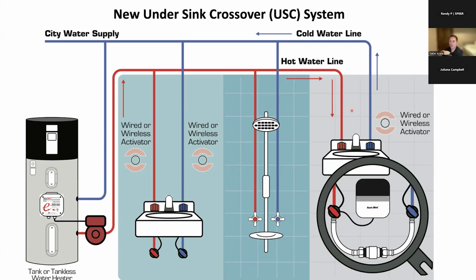So at the very end of the plumbing line, right? And most times this is the master bathroom. So what we have here is what we call the USC, which cross connects your hot water line into your cold water line. The way it works is anytime you want hot water, you push that button. And this little box here is a wireless temperature sensor. It's going to check your temperature, and if it sees that it's not hot, then it sends a wireless signal to the pump to turn on.